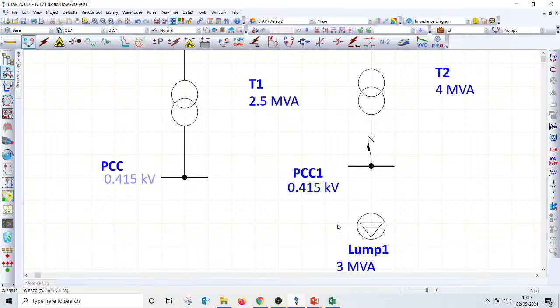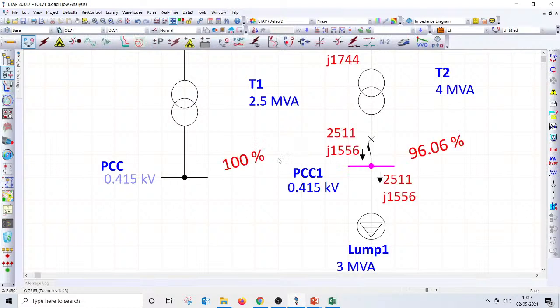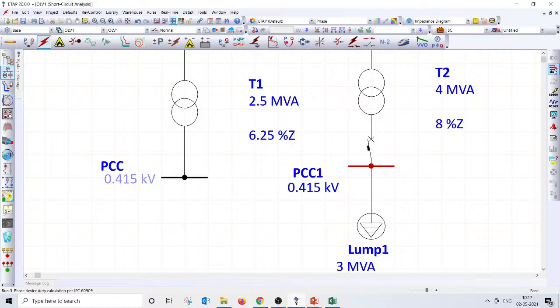As I said, you need to model the cables, motors, the motor short circuit current, everything in detail, but that may not permit us to do all those things. Load flow is not what we need to perform. We need to perform short circuit studies. If you look at it, this fault current is as high as 91 kiloamps, which means you need to go with a 100 kiloamp circuit breaker, not only in the incomer but also in all other outgoing feeders, right?